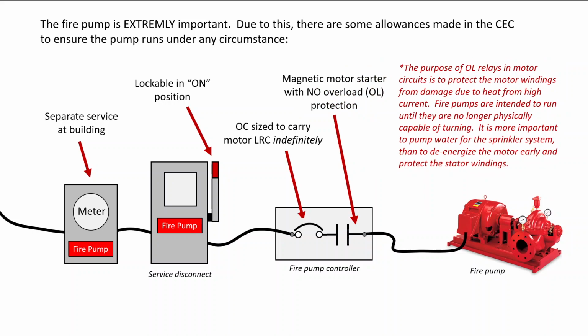The magnetic motor starter for a fire pump has no overload protection. The purpose of overload relays in motor circuits is to protect the motor winding from damage due to heat from high current. Fire pumps are intended to run until they are no longer physically capable of turning. It is more important to pump water for the sprinkler system than to de-energize the motor early and protect the stator windings.